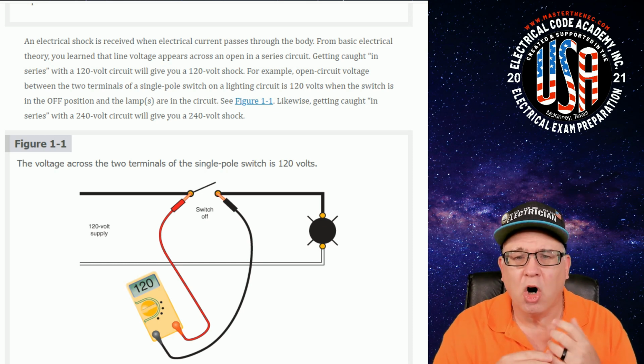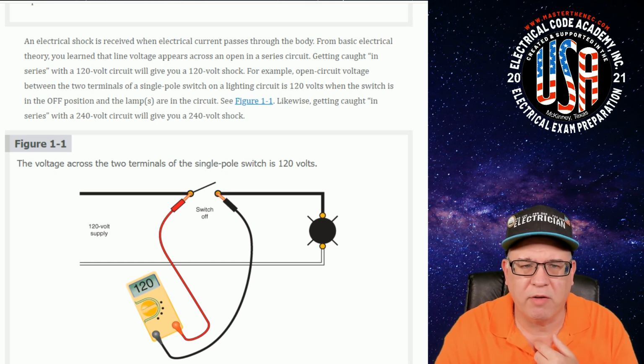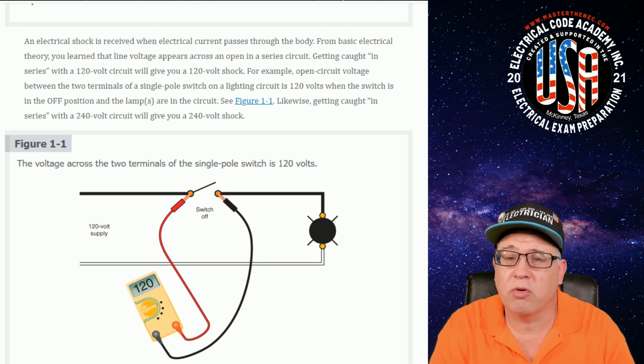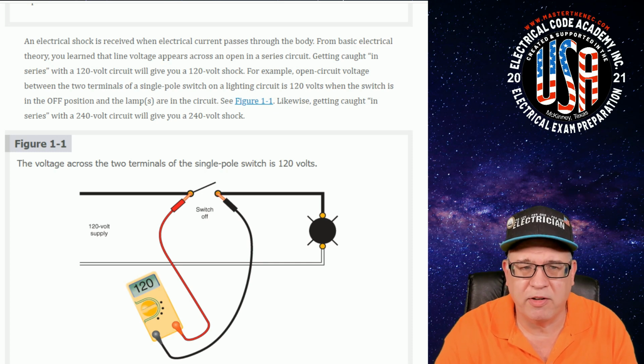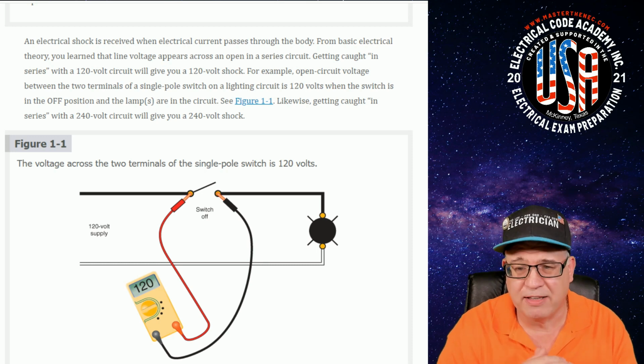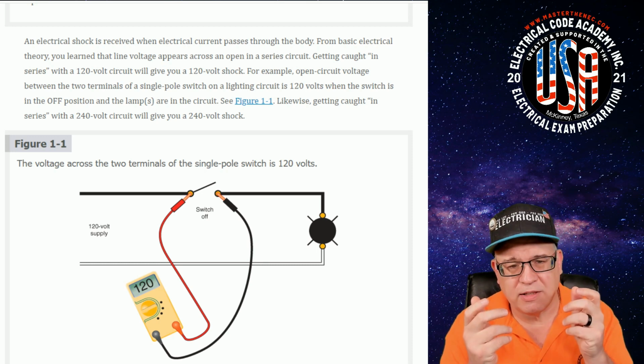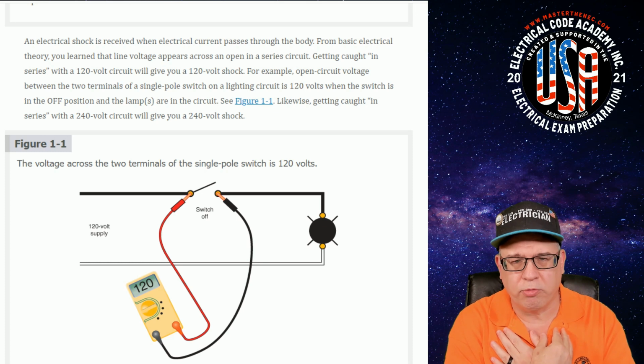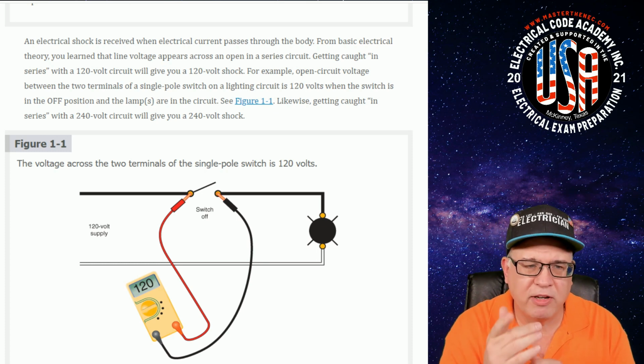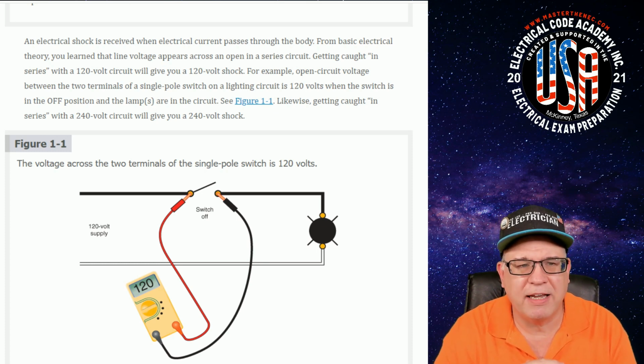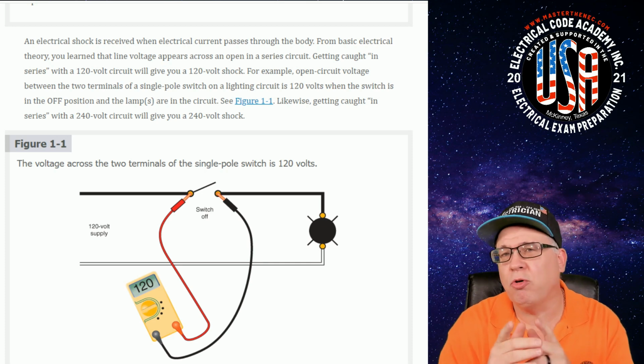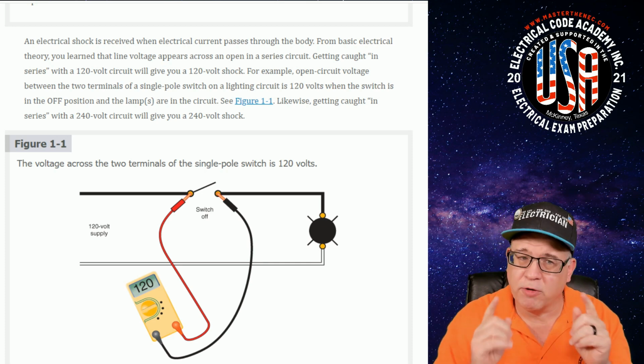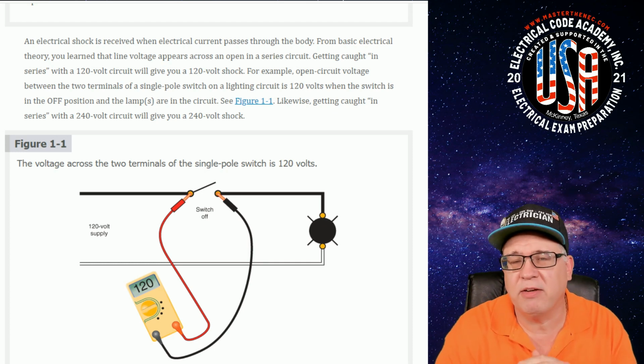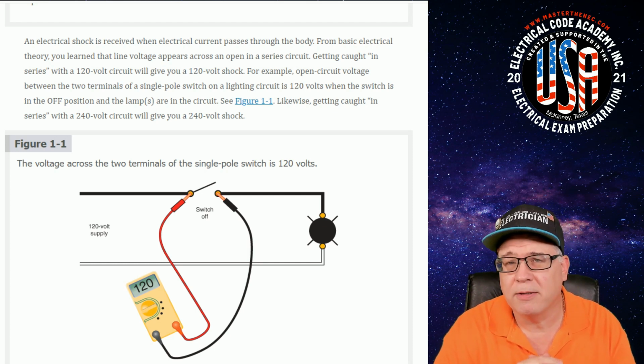For example, the open circuit voltage between the two terminals of a single pole switch on a lighting circuit is 120 volts when the switch is off and the lamp is in the circuit, completing it. Contact those two terminal points and current flows through you. As shown in figure 1.1, the same applies to a 240 volt circuit—if you're in series with it, you'll receive a 240 volt shock.